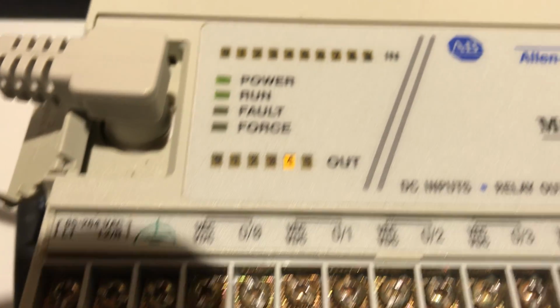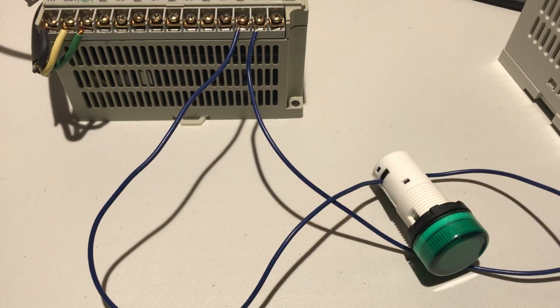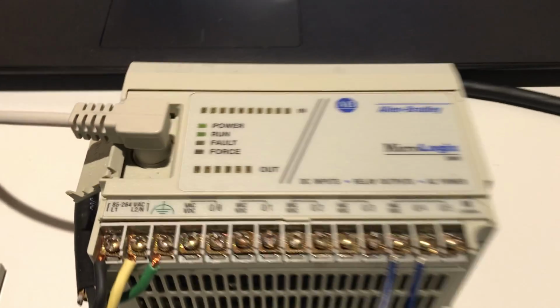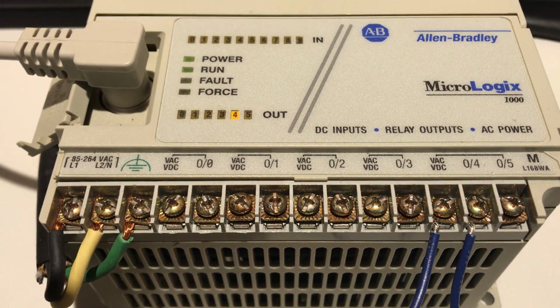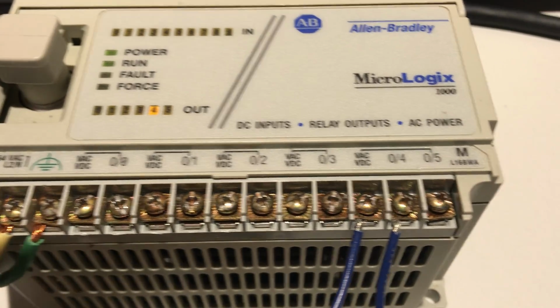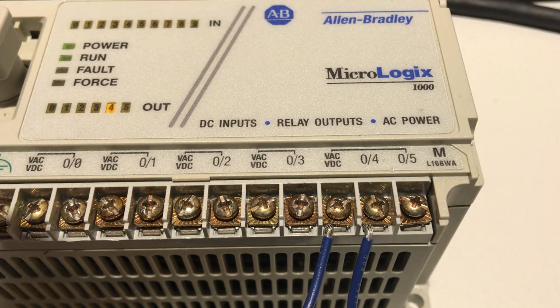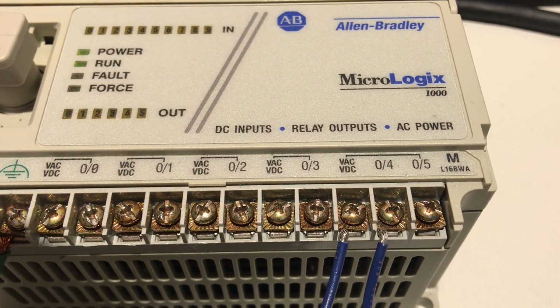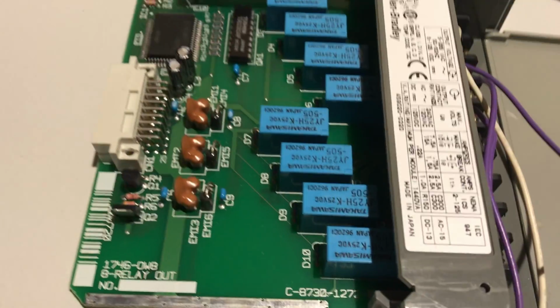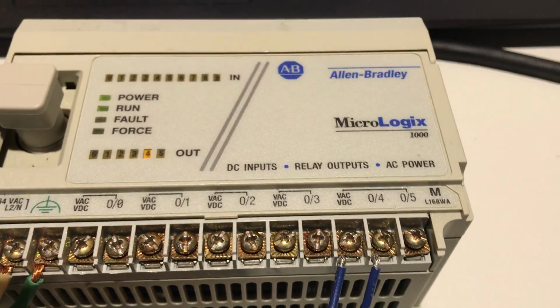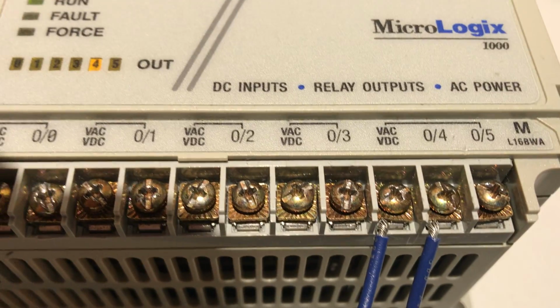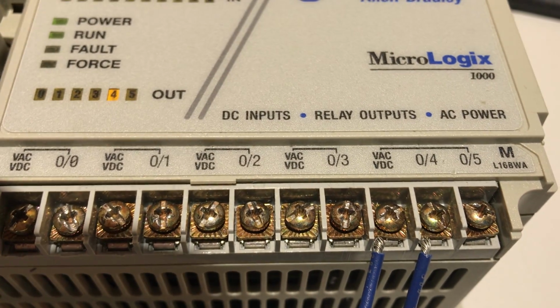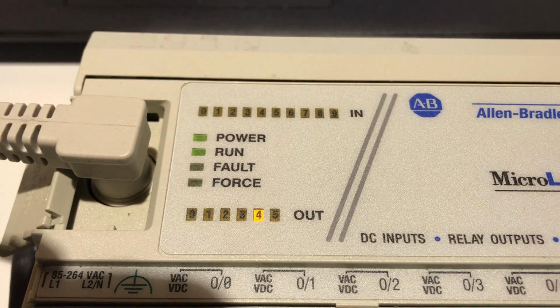And now you can see the output right there clicking on and off. See the light clicking on and off. And you can hear the click. The click is that contact in there between that last VAC, VDC, common terminal, and output 4. It's literally a little block relay in there that is energizing its coil, and the armature is opening and closing, and that's what the click noise is. You hear the mechanical click of it opening and closing, and you can see that it's indicated there.